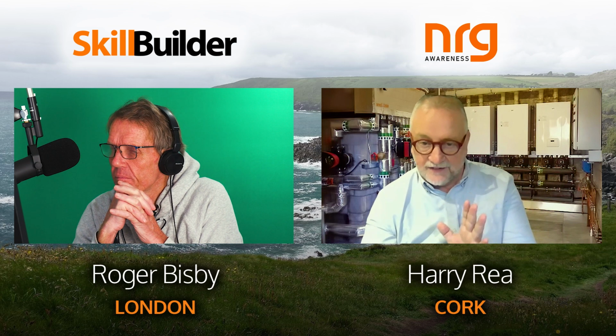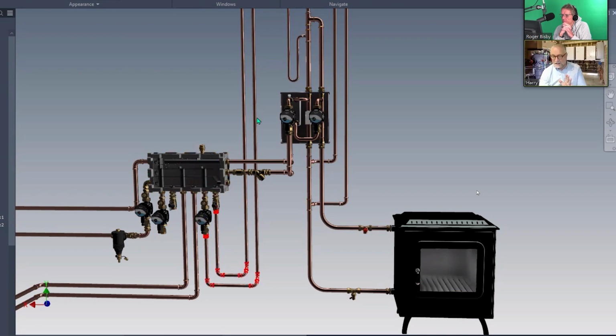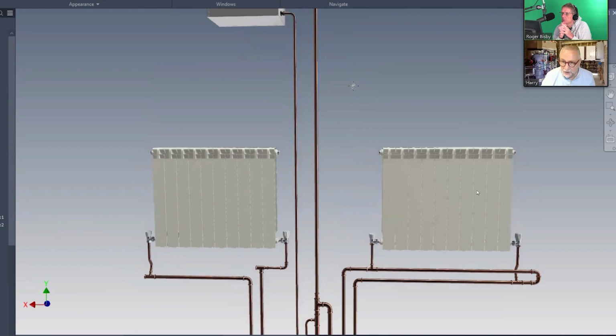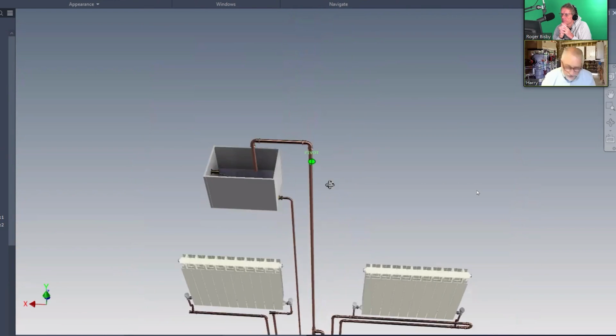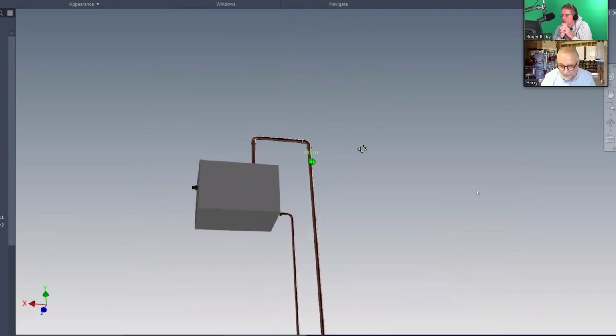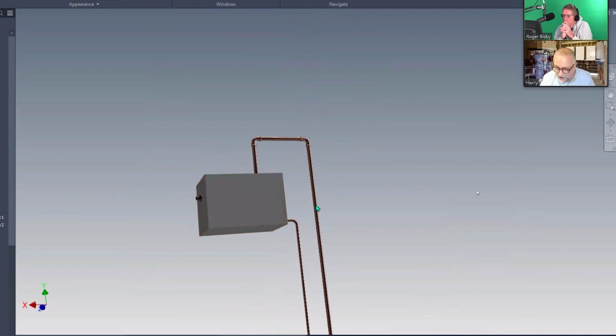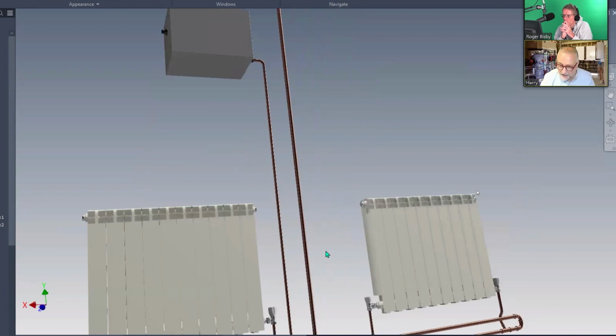See, let's look at this. Say we have, forget this for a second. This is an energy link, so it takes the heat exchanger, and we have open primaries. If I take this flow comes out of here, and if I was to bring that flow, there's literally an open pipe. Goes up, goes in a circle. Now, up here is interesting because we have our heating tank, our expansion, the water inside. So we have a reservoir, and the water in the expansion is up to this height here, same as the height in the expansion.